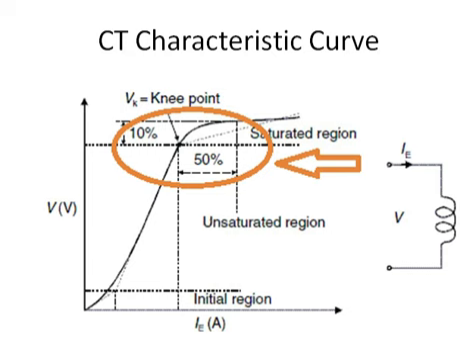That saturation point is the knee point voltage. As per IEC, the knee point voltage is defined as: the applied voltage across the CT where, if this voltage is increased by 10% and the excitation current increases by 50%, then this point is defined as the knee point voltage. Up to this point the CT will operate properly; after that it will get saturated.